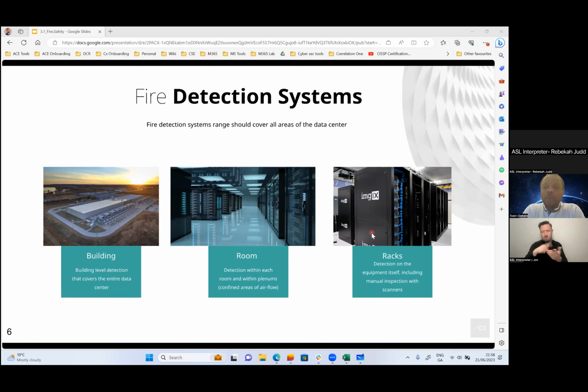But in most cases, they have other ways, some other type of firefighting equipment usually connected to the rack, maybe something gaseous or even powder in nature. A lot of the ones I've seen are chemicals with powder in nature. The reason is that after the fire, you are still going to count your losses and you want to salvage as much as possible, right? So you don't want to use any form of liquid to fight fire inside of your rack spaces. Most likely they will need something gaseous or chemical powder in nature for rack environments.